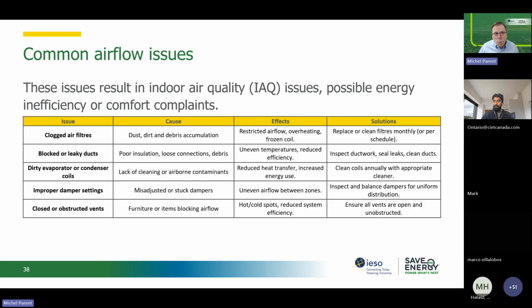A little quiz here. When you have a clogged filter and you change it with new filters, I wouldn't say better, but new filters, if your system is constant flow, it will increase the flow, it will increase the power usage. The odd thing about filters that are dirty, they save energy in terms of how much fan power is being used. It's a bit counterintuitive, but if your system is variable speed, it's the total reversal. You will spend a lot more energy on your fan with dirty filters on a VAV system.